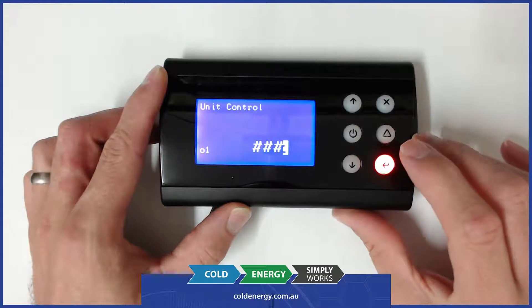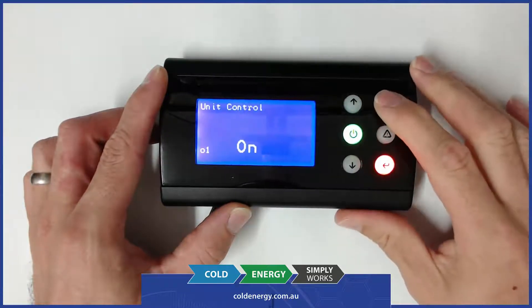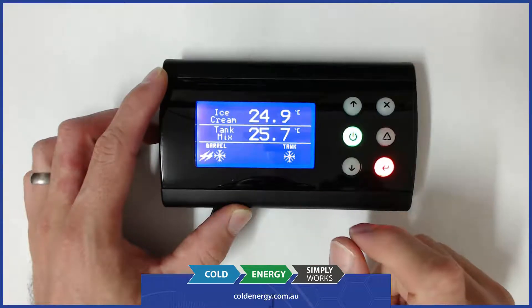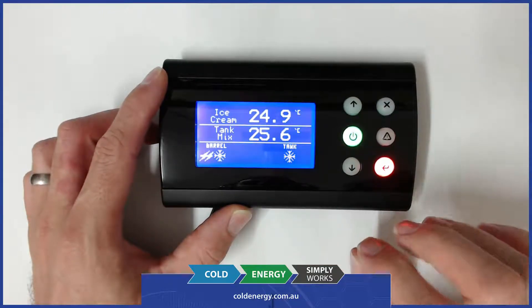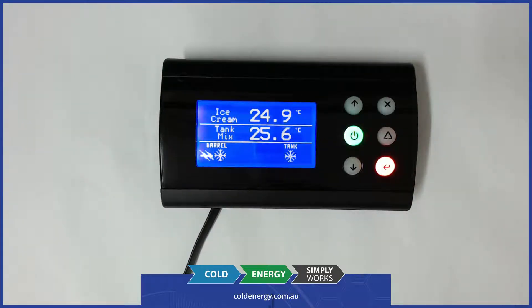We're just going to turn it on for the moment. You can see now we've got some green LED indication to show that the unit is on, and on the main screen we've now got additional information showing the tank cooling is on, the barrel cooling is on, and the beater is moving and agitating. The feedback from the tacho on the beater motor is showing that it's within range — if that is reduced or too high, that will stop the refrigeration and some protective action will be taken.